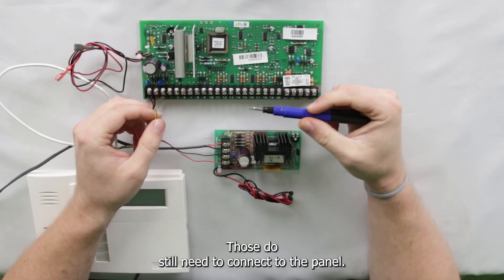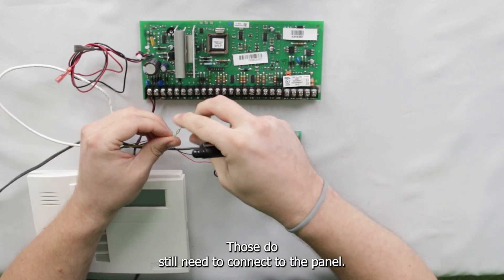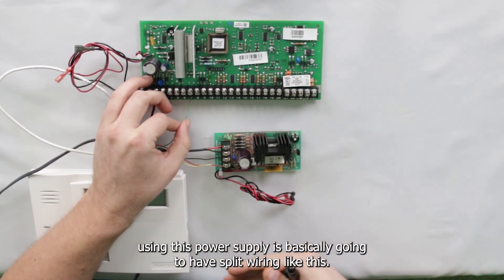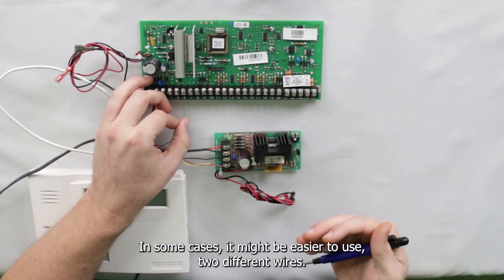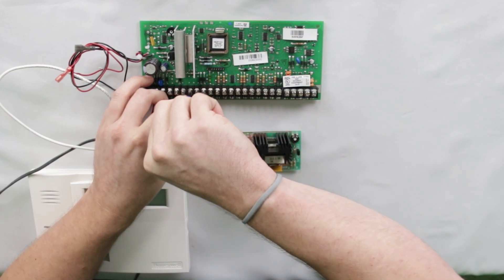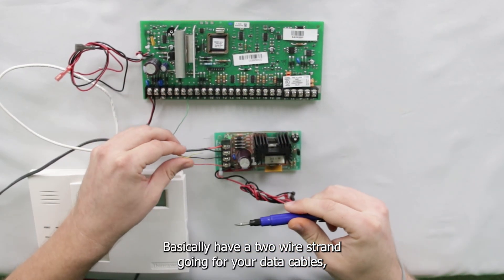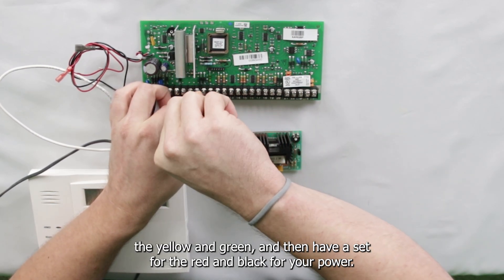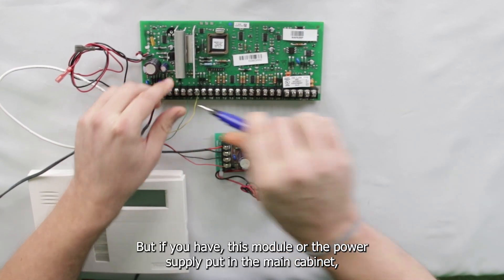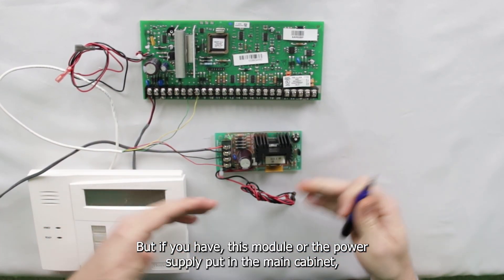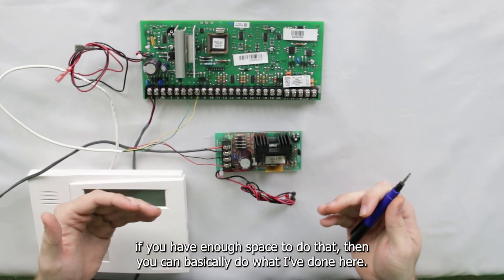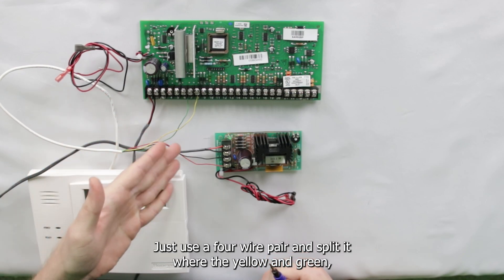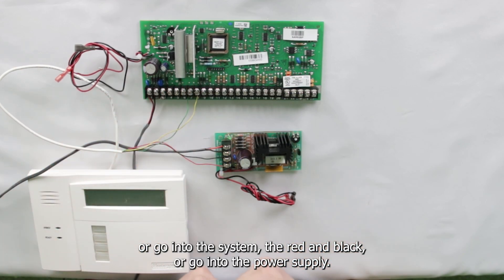Now your yellow and green wires, those do still need to connect to the panel. So any module you have powered using this power supply is basically going to have split wiring like this. In some cases, it might be easier to use two different wires, have a two-wire strand going for your data cables, the yellow and green, and then have a set for the red and black for your power. But if you have this module or the power supply put in the main cabinet, you can basically do what I've done here. Just use a four-wire pair and split it where the yellow and green are going to the system, the red and black are going to the power supply.